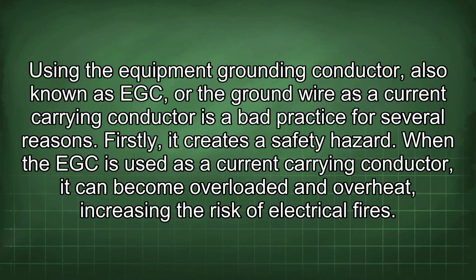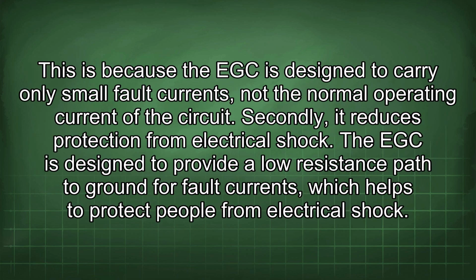Using the equipment grounding conductor, also known as EGC, or the ground wire as a current carrying conductor is a bad practice for several reasons. Firstly, it creates a safety hazard. When the EGC is used as a current carrying conductor, it can become overloaded and overheat, increasing the risk of electrical fires. This is because the EGC is designed to carry only small fault currents, not the normal operating current of the circuit. Secondly, it reduces protection from electrical shock.